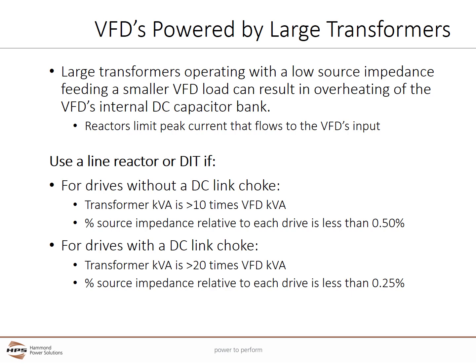Example: the smallest distribution transformer is generally 15 kVA. 10% of 15 kVA is 1.5 kVA, which is roughly 2 horsepower. Since many VFDs below 10 horsepower don't have a DC link choke, and 15 kVA is typically the smallest distribution transformer, it's suggested that at the very least, VFDs 2 horsepower and below should have a line reactor. DITs, as we will learn, are often not practical for these smaller horsepower VFDs. By the same token, the most common distribution transformer is typically 5 times larger than 15 kVA at 75 kVA. This would indicate that in most cases, VFDs 10 horsepower and below will often benefit from having a DIT or line reactor.